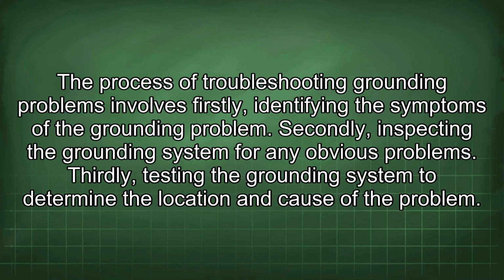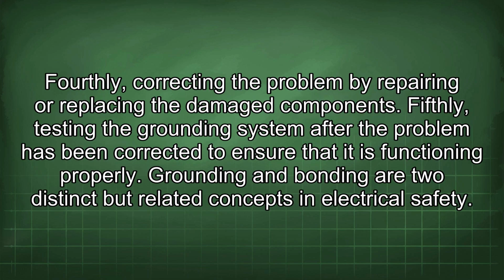The process of troubleshooting grounding problems involves, firstly, identifying the symptoms of the grounding problem. Secondly, inspecting the grounding system for any obvious problems. Thirdly, testing the grounding system to determine the location and cause of the problem. Fourthly, correcting the problem by repairing or replacing the damaged components. Fifthly, testing the grounding system after the problem has been corrected to ensure that it is functioning properly.